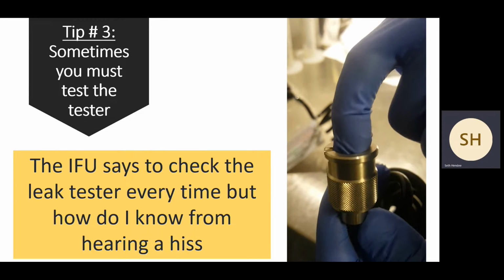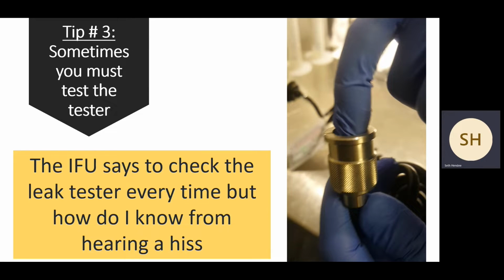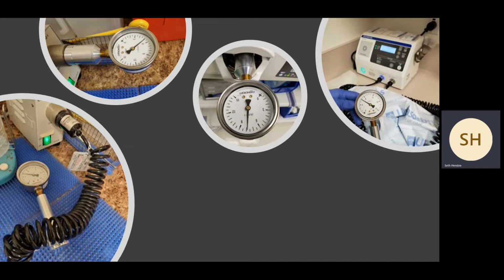Now, hopefully you could hear that little hiss right there, but I would really like you to think, is that as loud as it was yesterday? If somebody else did the testing yesterday, what do you really have to compare to? So, as it turns out, these units, from the manufacturer, they place a number on whether their unit is functioning properly or not. So with the data from the company that says, if you're below 4 psi on this unit, we would consider it in need of repair. If there's a gauge out there where you can look to check that pressure, the gauge will tell you 4 psi. Your finger's going to have a little bit of trouble doing that, right?